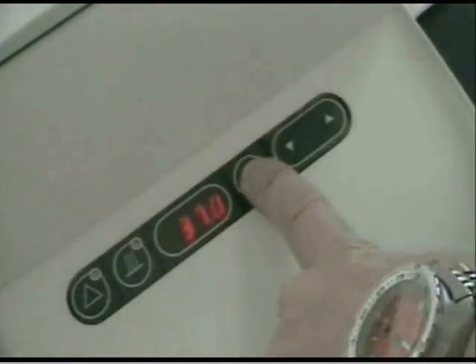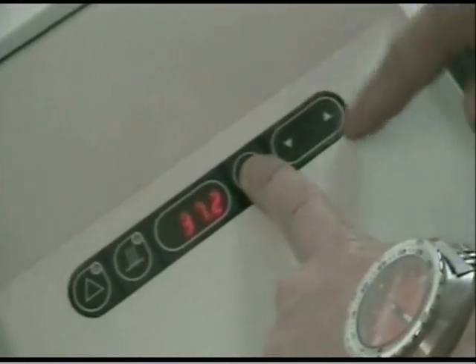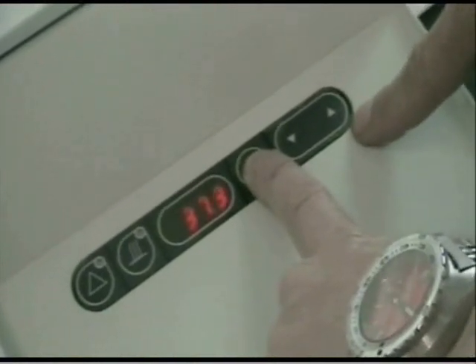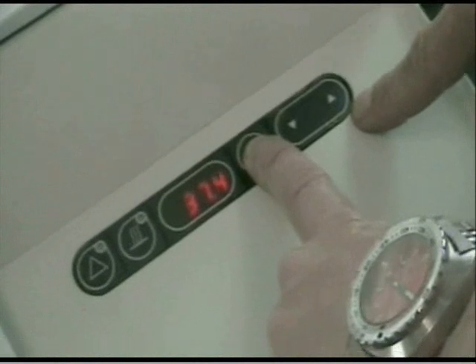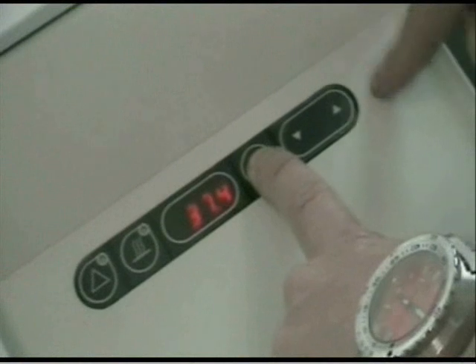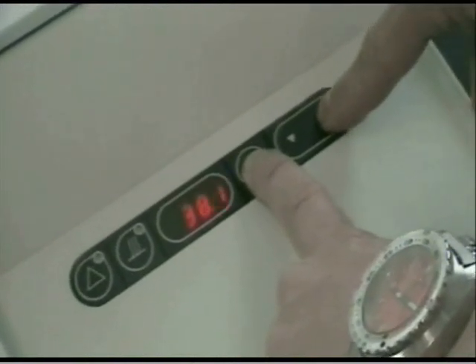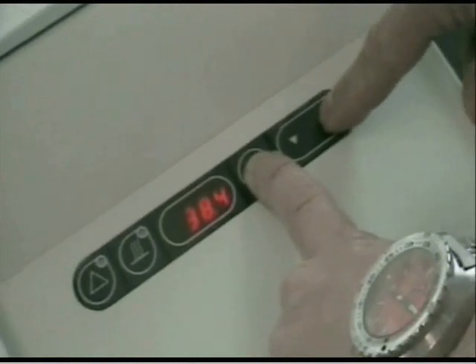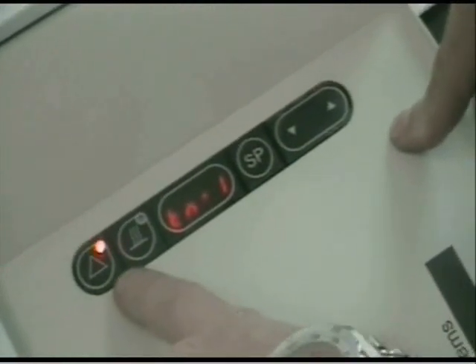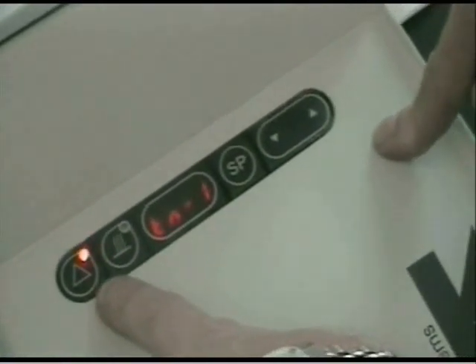So now we adjust the value to 38.7 as we've measured. This we do by pressing the up key. One press on the key corresponds to a change of 0.05. So you need to press 2 times to get a change of 0.1 degrees in the display. I just keep pressing until it reads 38.7. And then I let go. You'll get an alarm now because it thinks the temperature is out of control. Just mute that. It's no big deal.